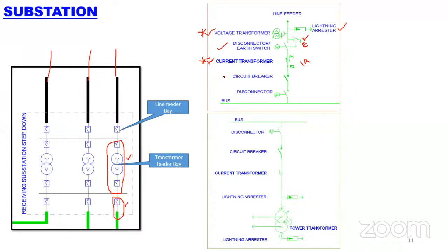Okay, then the next device is the switchgear, the circuit breaker. This is the crucial one, which helps you in the normal and abnormal states of the system. Basically, the circuit breaker is capable of making and breaking the load, which means closing and opening the particular feeder when it is in operation. Maybe we have studied air blast circuit breakers, then hydraulic circuit breakers, then the SF6 circuit breaker. Predominantly SF6 circuit breakers are used in high voltage networks. Then the next switchgear is the disconnector, which helps to connect it to your bus bar.